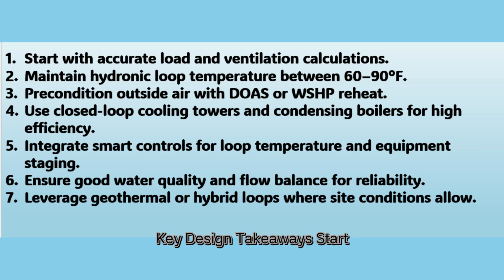Key design takeaways. Start with accurate load and ventilation calculations. Maintain hydronic loop temperature between 60 to 90 degrees Fahrenheit. Precondition outside air with DOAS or WSHP reheat. Use closed-loop cooling towers and condensing boilers for high efficiency. Integrate smart controls for loop temperature and equipment staging. Ensure good water quality and flow balance for reliability. Leverage geothermal or hybrid loops where site conditions allow.